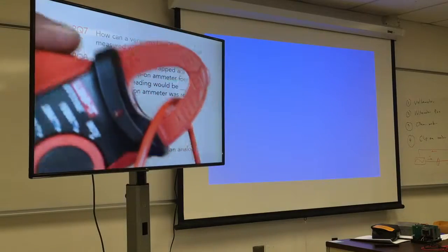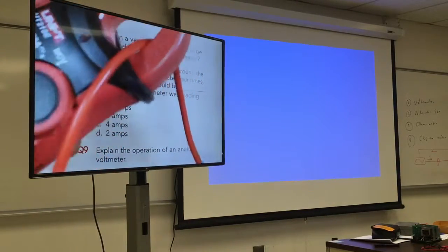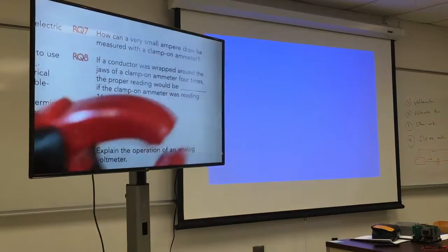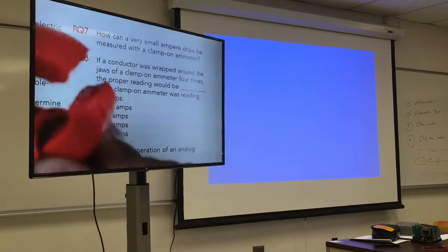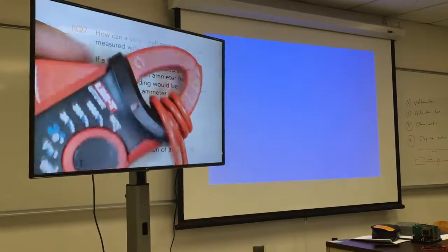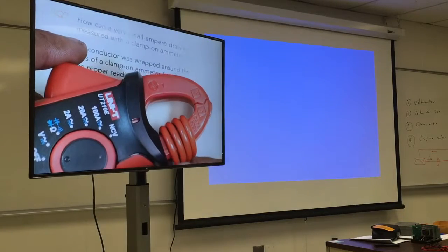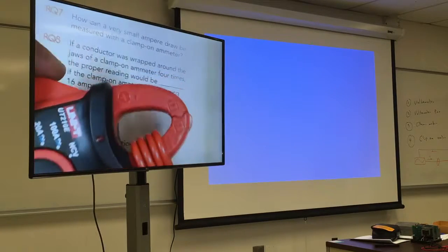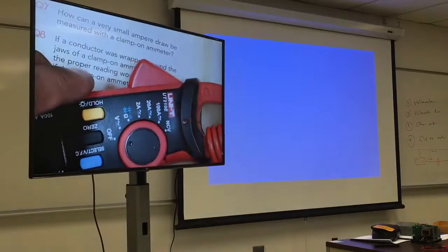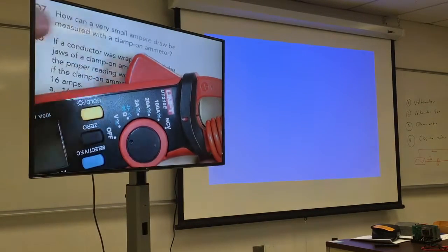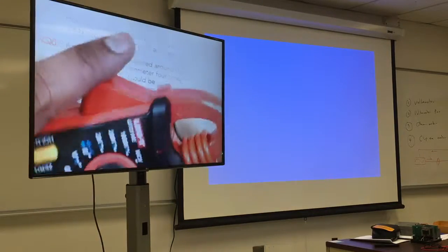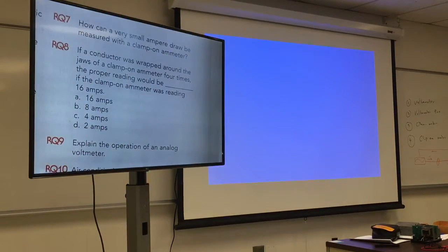You click around the wire. But it's very small, I'm seeing zero. So you go around—wrap it around multiple times, loop 1, 2, 3, until you get a reading. How many loops do we have? 1, 2, 3, 4—whatever number you get, you divide by 4. This is a good way to get a good reading and also to verify it. If you get 0.015, you want to make sure you double-check, and if it reads well, you get the right reading.